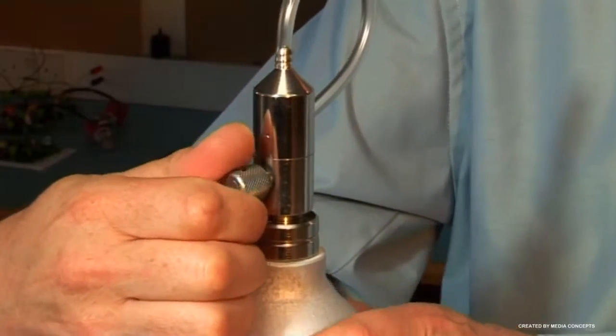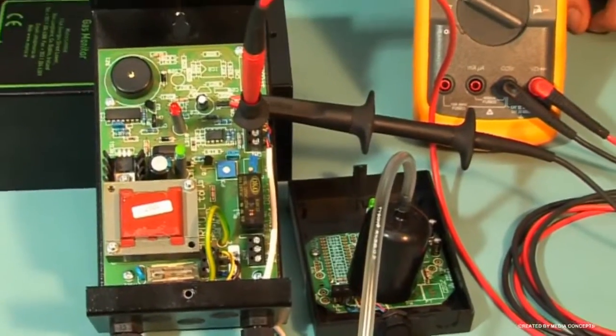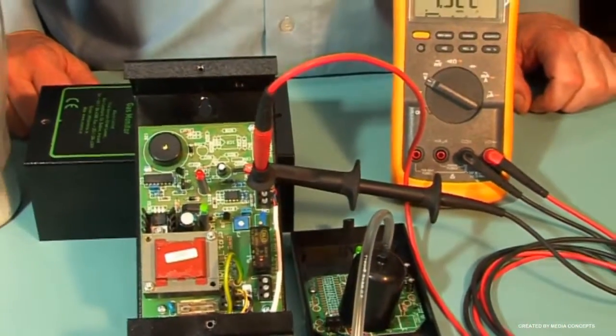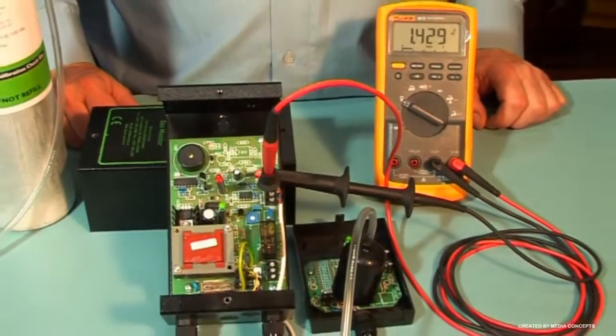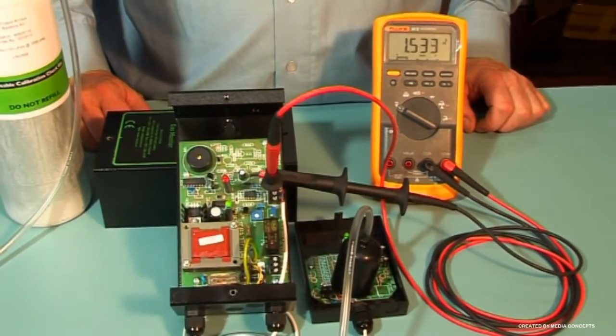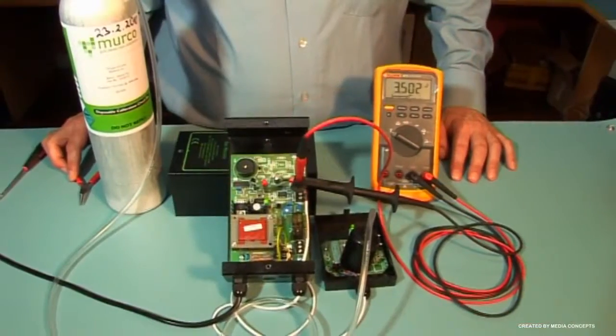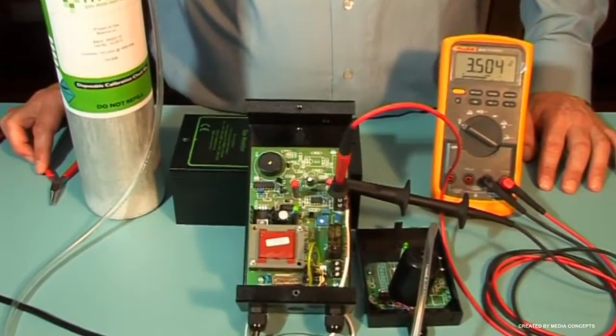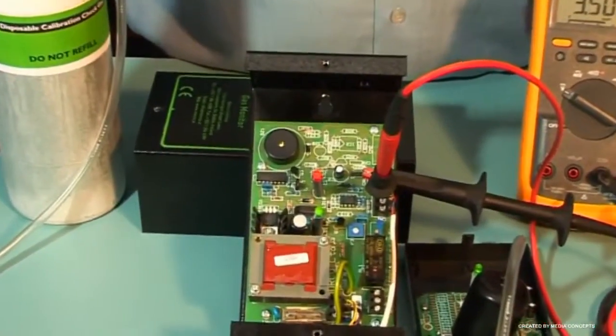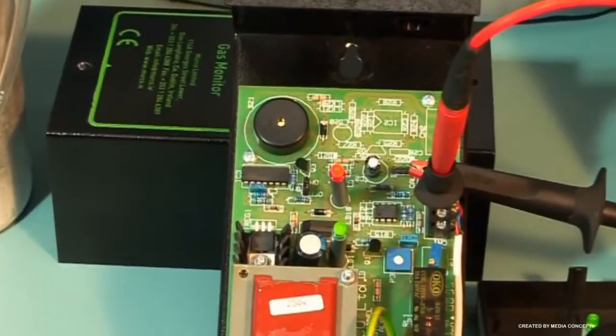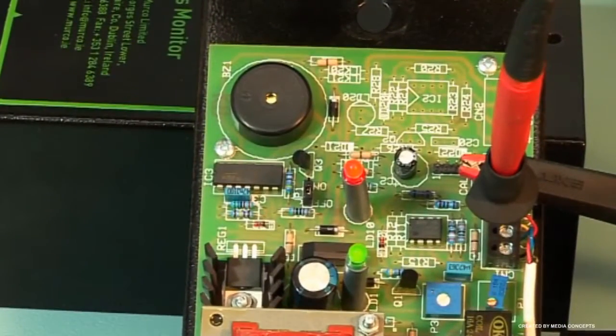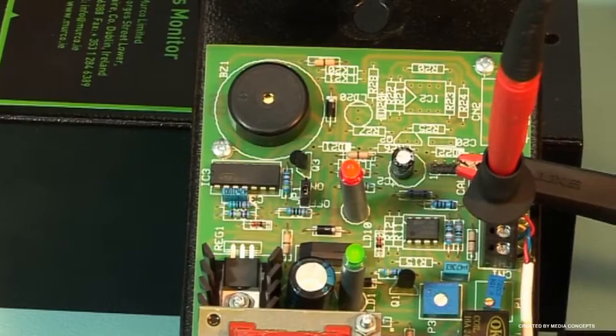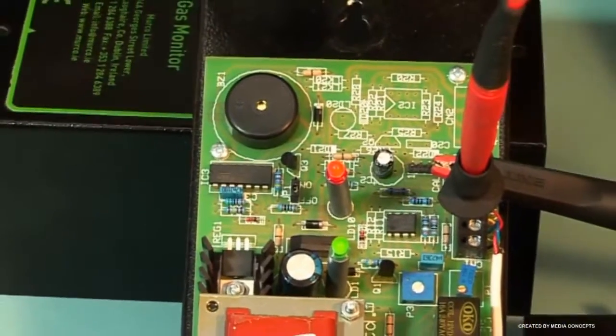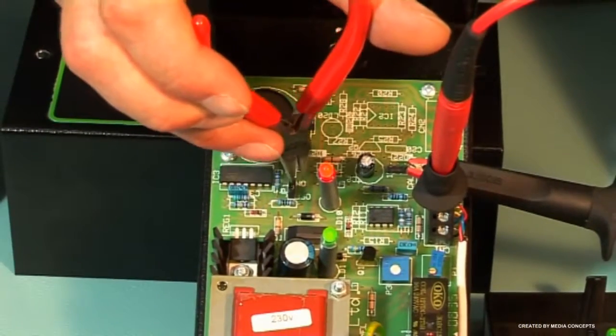You should see the standby voltage increase. It may take 10 to 15 minutes to pass the alarm set point. Older sensors may take longer. Once you've reached the alarm set point, the low-level yellow LED will come on, and then the red LED will come on at a high-level set point, and the sounder, if enabled, will activate. The relay should also activate on the controller. The sounder can be muted by removing jumper JP1.